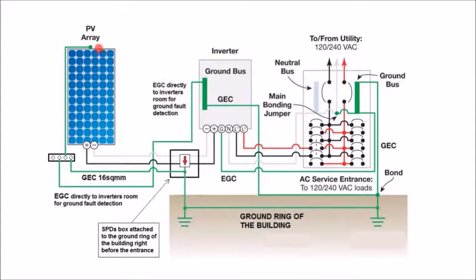We have our grounded module frame going onto a ground bar. So this might be inside a PVC box. So instead of the ground rod going on from the metal frame to the rack to the box frame, we're just making the ground inside this ground bar. And then that's carrying the equipment ground to the metal inverter box. And then this is also going, maybe that's a permanent crimp, but it's also being connected to the ground bus on your main service panel.